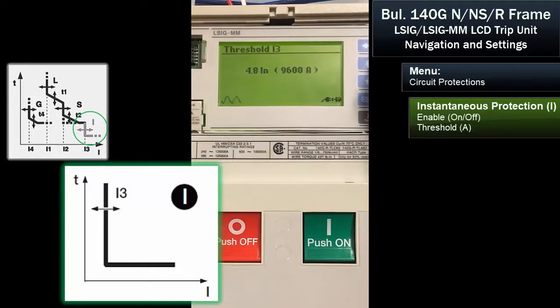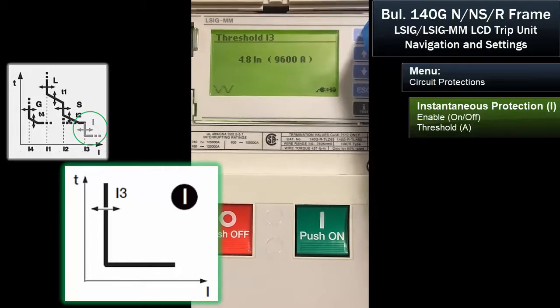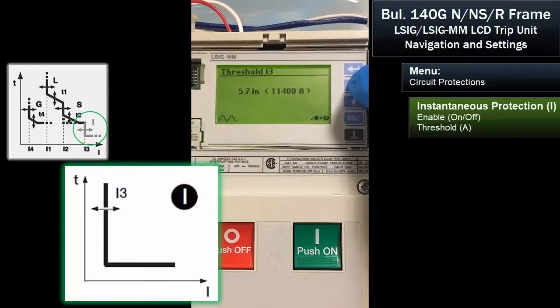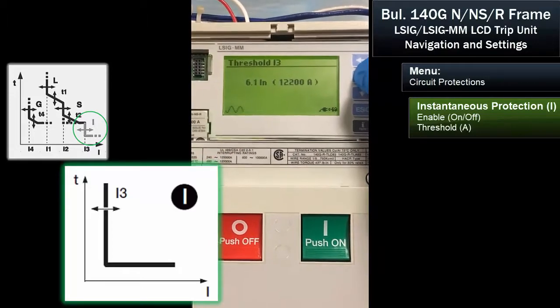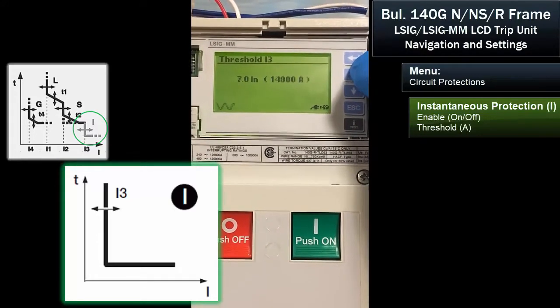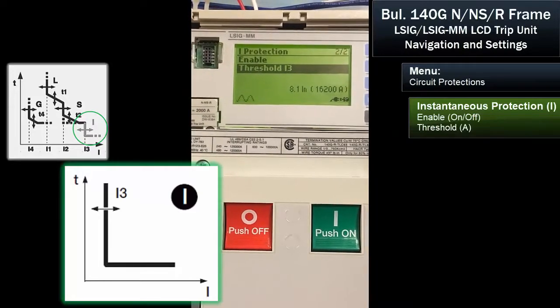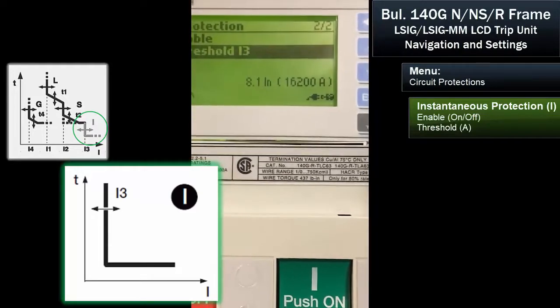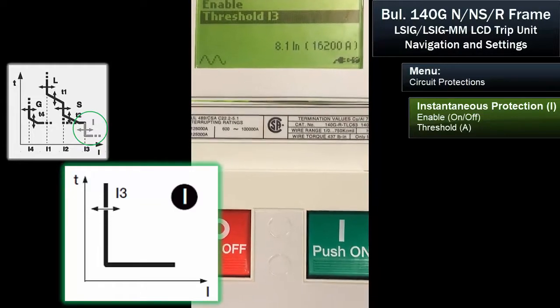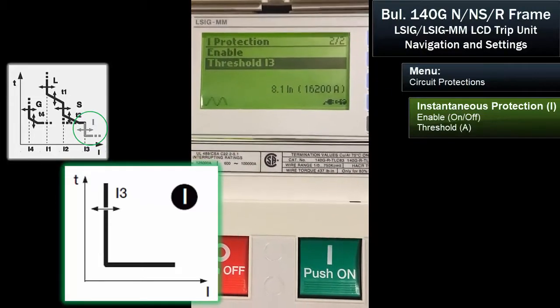We always want our instantaneous protection to be greater than our short-term rating so we don't have nuisance tripping — you can see that when you look at the curves documentation. On a breaker of this size, we normally never have a motor driven directly from it. So let's set it at eight times. And you can see that we've set the I3, or instantaneous trip, at eight times.